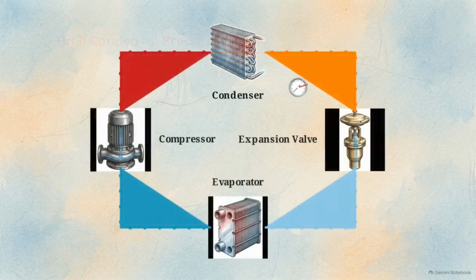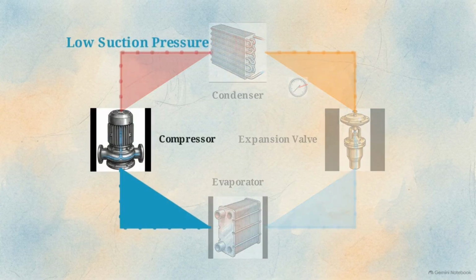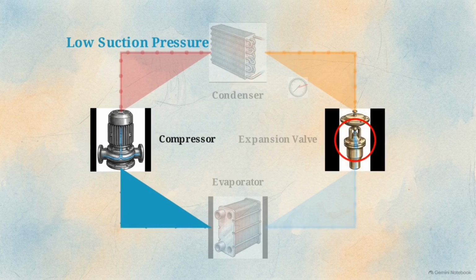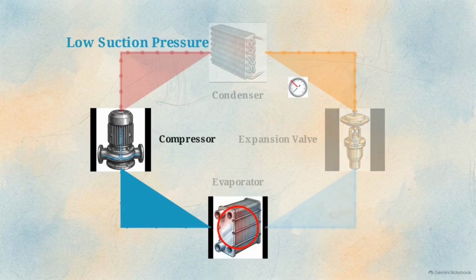Conversely, low suction pressure points to a failure at the intake line just before the vapor enters the compressor. This low pressure means there is a lack of mass flow in the pipes. It points to a low refrigerant charge, a restricted expansion device starving the system, or simply a lack of actual heat load from the building to boil the refrigerant.